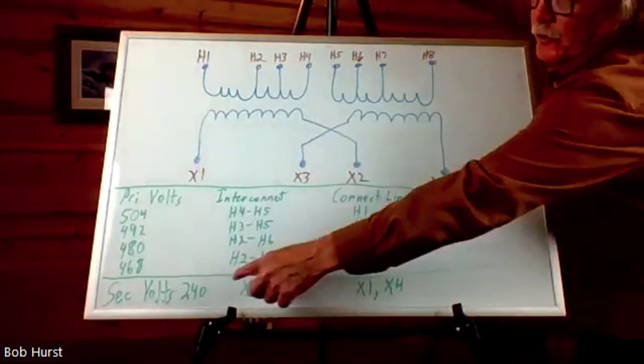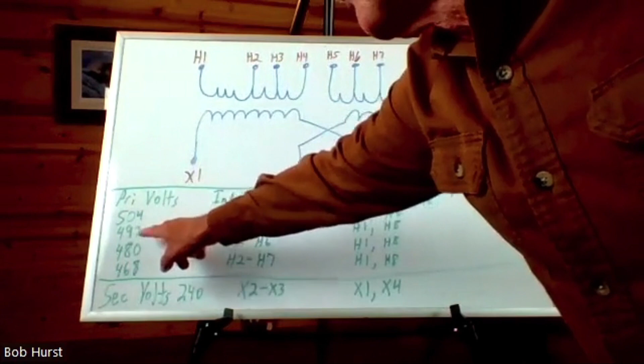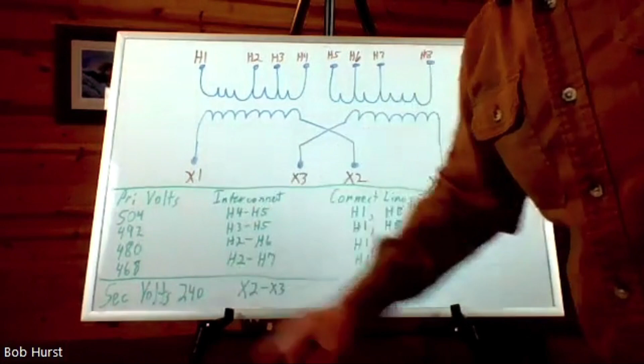So the deal is we're wanting 240 volts. This is telling us, it gives on the drawing right here, the primary volts - if we've got 500 volts, 504 coming in, 492, 480, 468. So if we've got any of these voltages, it's telling us how to tap it so that we can get 240 volts. That's where a lot of people get a little confused.